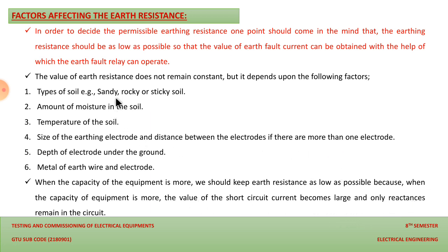So these are the factors that affect the earth resistance, which we should keep in mind while we are placing the earthing. And this is the type of equipment. If the equipment capacity is more, the short circuit current will be large, and if the capacity of the equipment is less, then the short circuit current will be less.